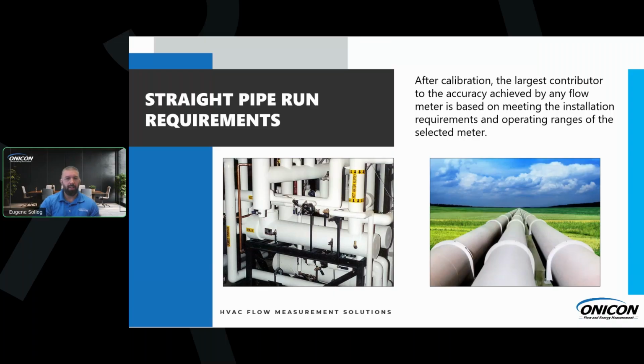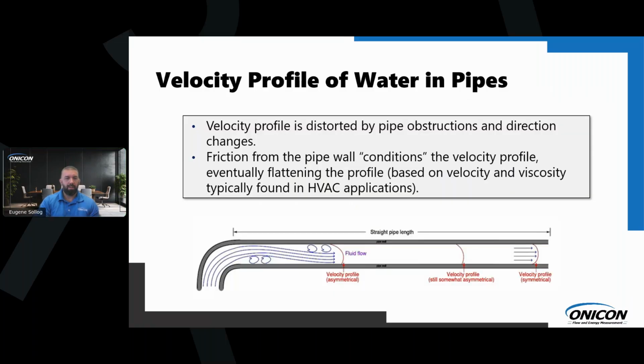Oops, sorry, I clicked out of that. And just to look at a single 90, for example, you can see all the swirl that's induced in this. Ideally, we'd always like a symmetrical velocity profile for our meters, or any meter, really. Any meter manufacturer would want to see that. Luckily, we have other technologies like the inline mag, which could compensate for this, because it averages the flow through the whole cross-sectional area a lot better than any other flow meter really can.